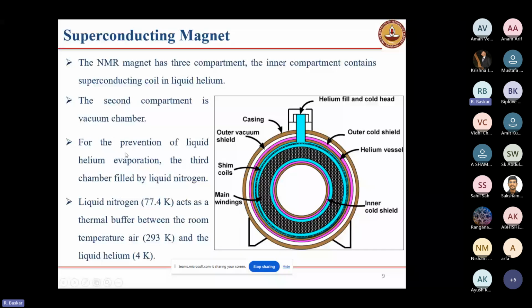The first one is the liquid helium chamber. After that, vacuum. Then the next one is the liquid nitrogen chamber. Why are we filling the liquid nitrogen? We cannot stop the helium evaporation, and helium is very expensive, but we can reduce the helium evaporation. That is the reason we fill liquid nitrogen in the third compartment, so that the liquid helium will stay.